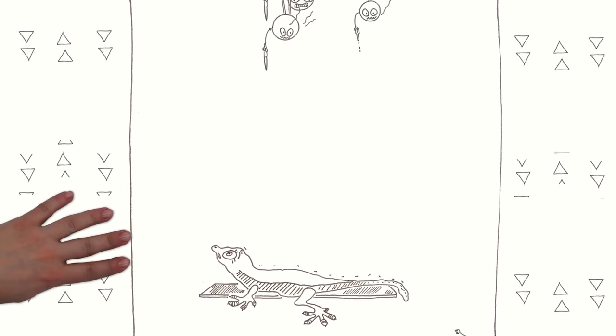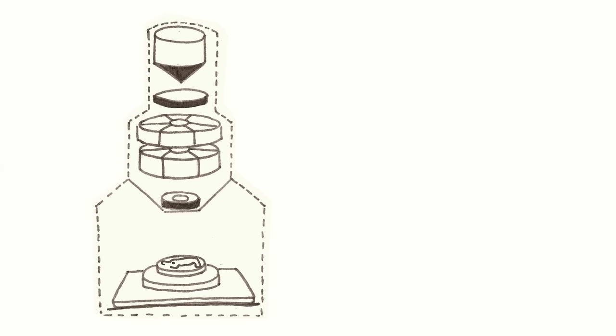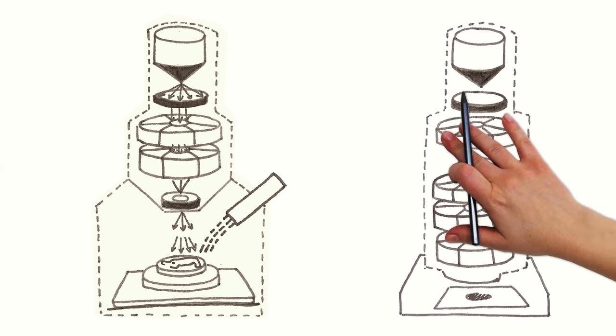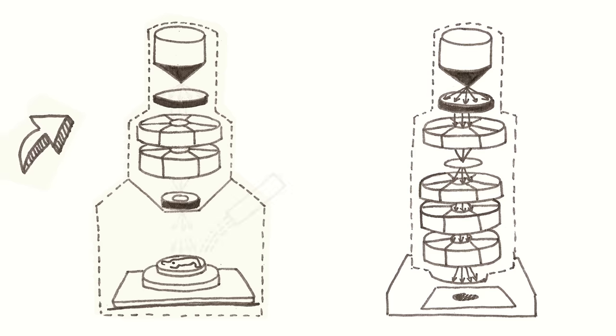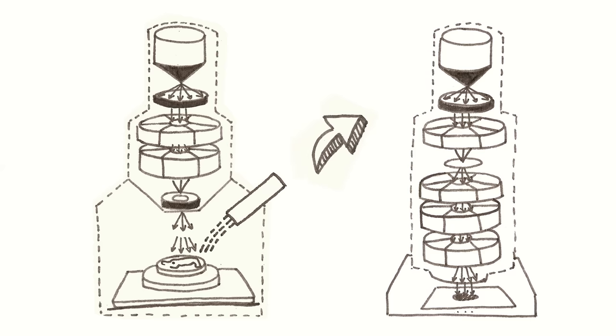Electromagnetic lenses focus the electron beam on the examined sample in an optimal way. During its entire journey, the electron beam goes through a number of apertures with various diameters. The smallest ones can be just a few thousandths of a millimeter. These apertures stop electrons undesirable for creating the image. The electron beam hits the observed object and it either scans its surface step by step as if it were reading an inscription on the wall with a torch at night, or it goes through the sample and shows its inner structure.